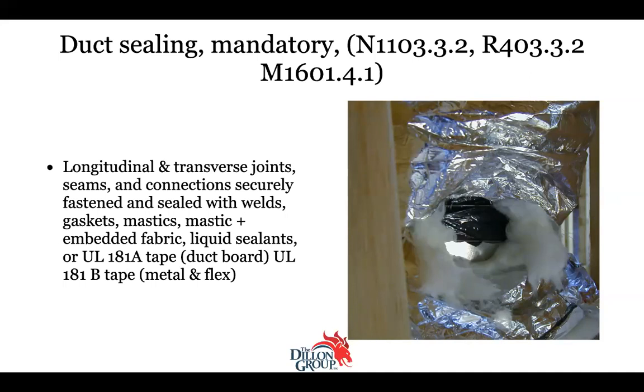And odds are that even if they have to trim off a few inches of flex to reestablish that connection, they almost always leave it a foot or two too long anyway, and it needs to be as straight as possible. A foot or two? Yeah, I'm being generous. I mean, flex duct comes out of the box 25 feet long. I had one duct run. It was 8 feet, and they used the full 25-foot length, and it was just snaking along.